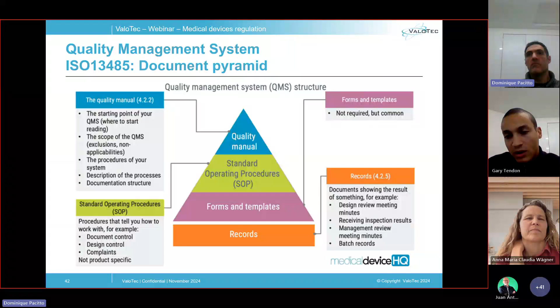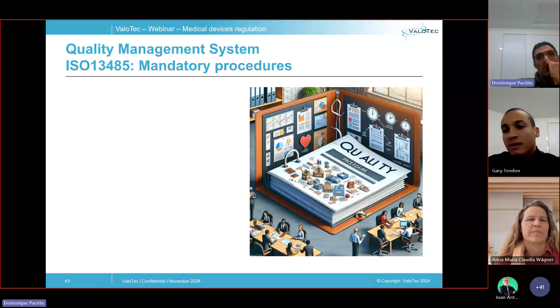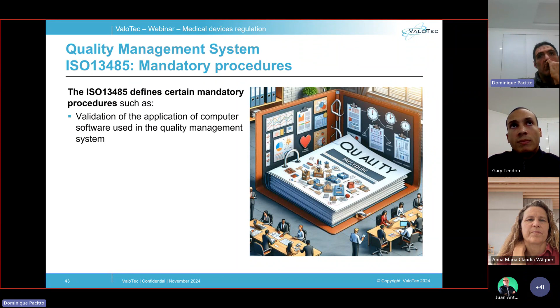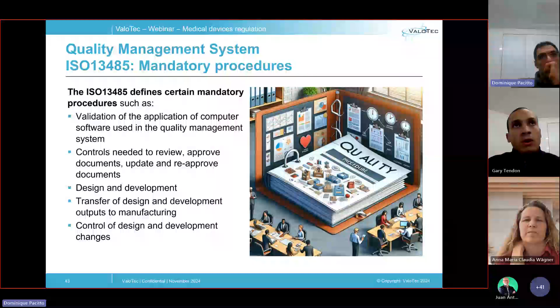You have to know that the QMS should not be a static set of documents. It must be regularly reviewed and updated to ensure its effectiveness. Furthermore, the ISO 13485 standard requires 31 documented procedures. These documented procedures are the pillar of the quality management system. It's not necessarily 31 different documents, but one document, for example, can contain multiple mandatory procedures. Here you can see some examples of these mandatory procedures.